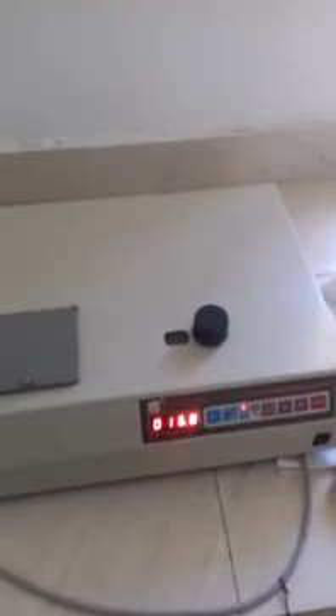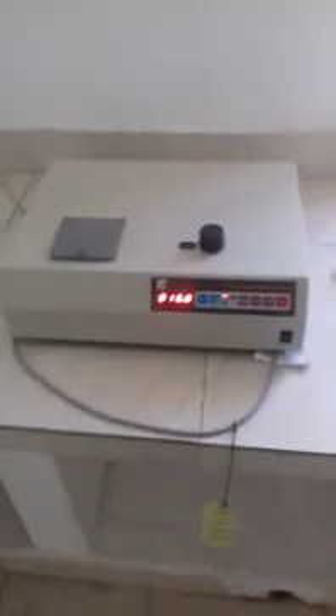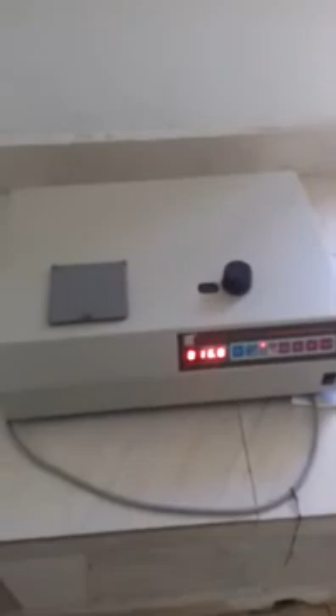This is a spectrophotometer. This is called a visible spectrophotometer. There are two types, visible and UV. For some chemicals, ultraviolet is required, and even for analysis of nitrate, an ultraviolet spectrophotometer is required. You can see how the transmittance or absorbance is measured, and based on the measurement, earlier we have calibrated the instrument.